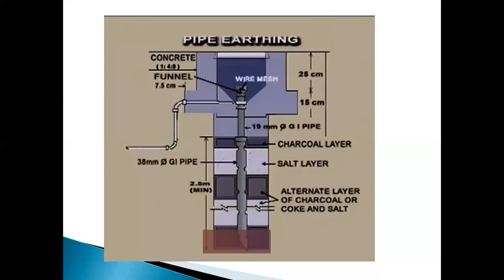The earth wire used must be galvanized iron wire or galvanized iron strip of sufficient cross-sectional area to carry the fault current safely. This earth wire from the 19 millimeter diameter GI pipe should be carried in a 12.7 millimeter diameter galvanized pipe at a depth of 60 centimeters from the ground level. Further, when the wire is carried from one machine to another, it should be well protected from mechanical injury by carrying the earth wire in a recess portion.